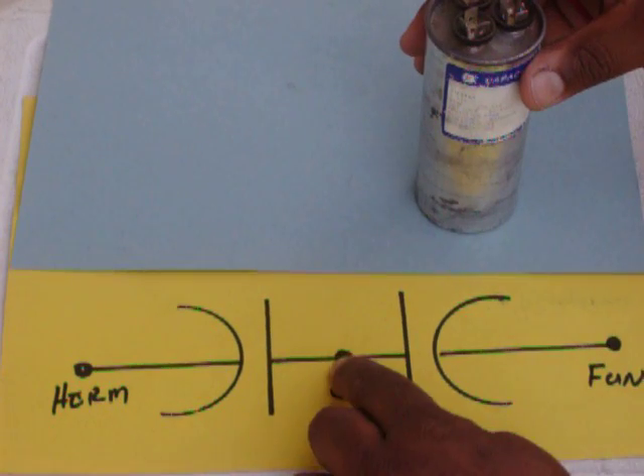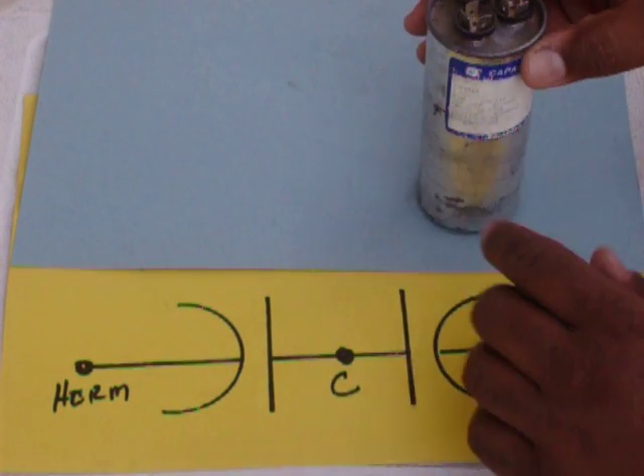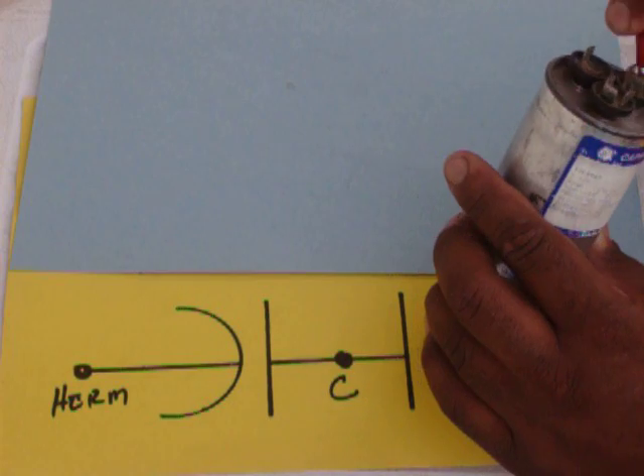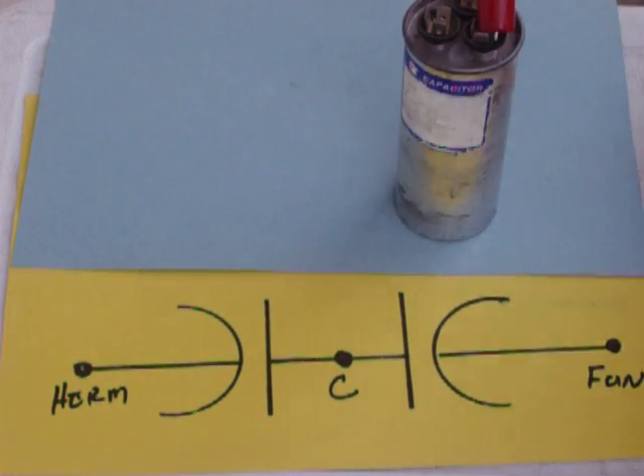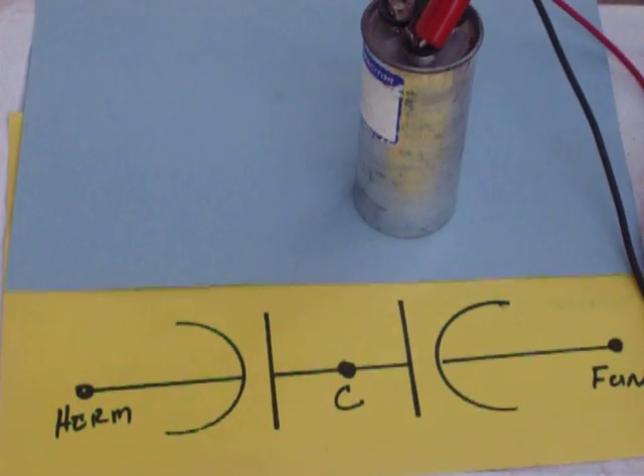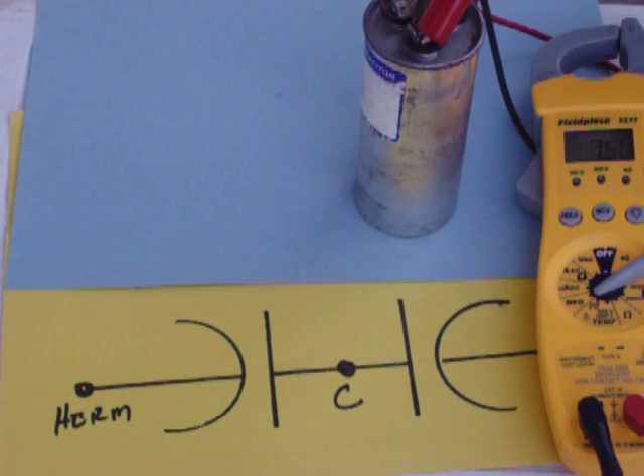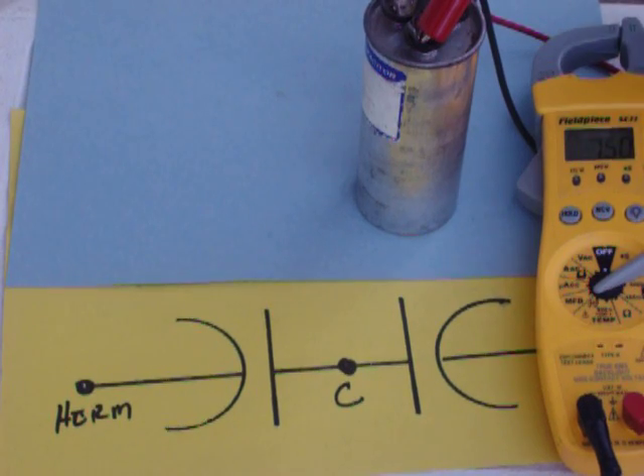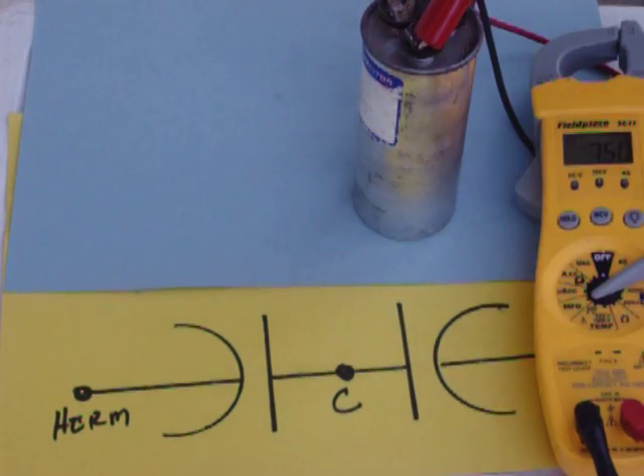Now we want to check from common to fan and we should get that 7.5 that we see. So I clip on common and then I clip on fan. Let my meter read it. 7.5 on the dot. So the fan side of it is good.